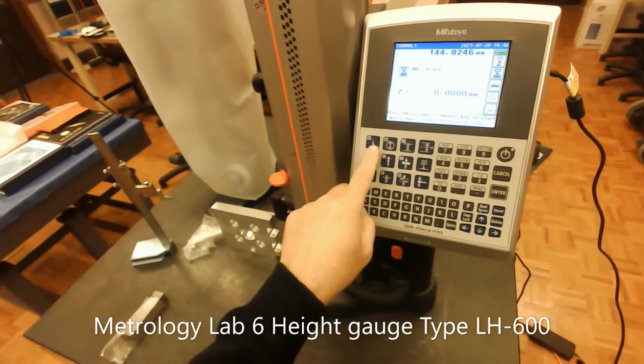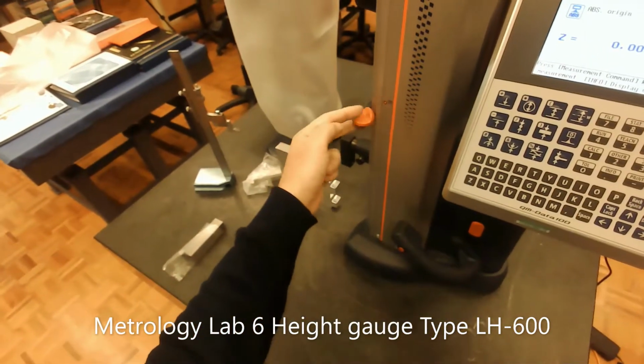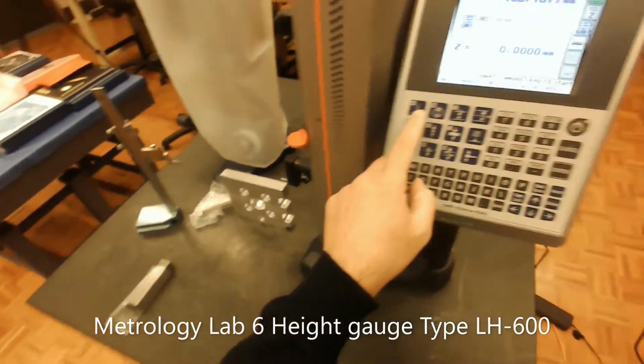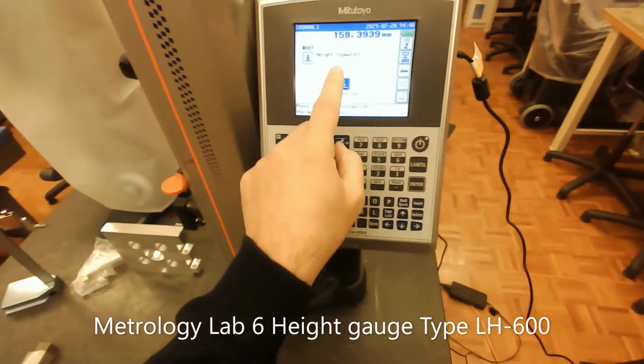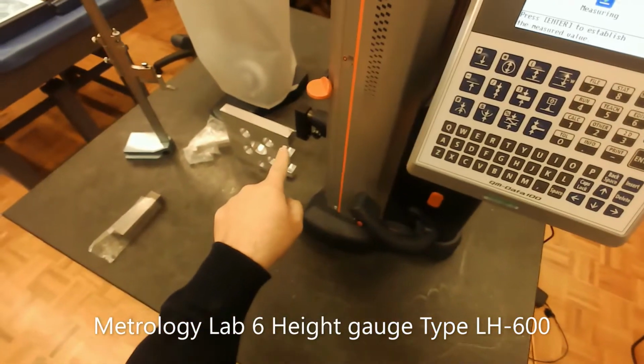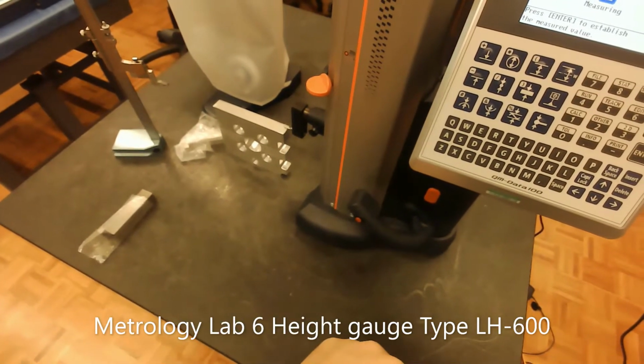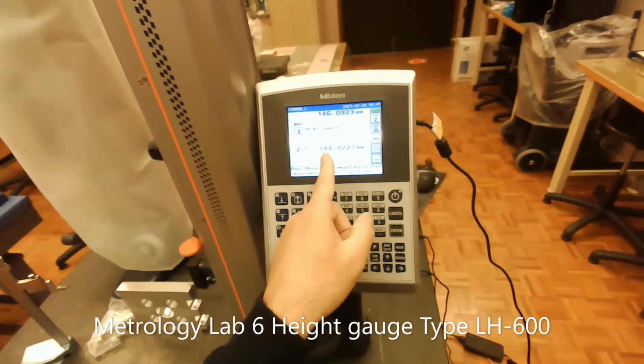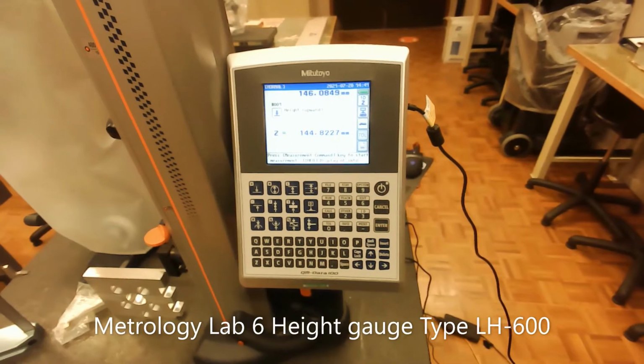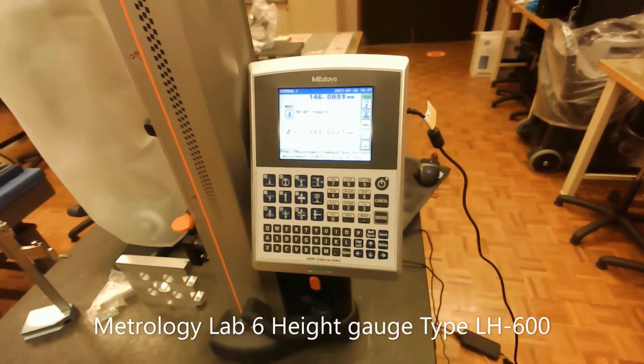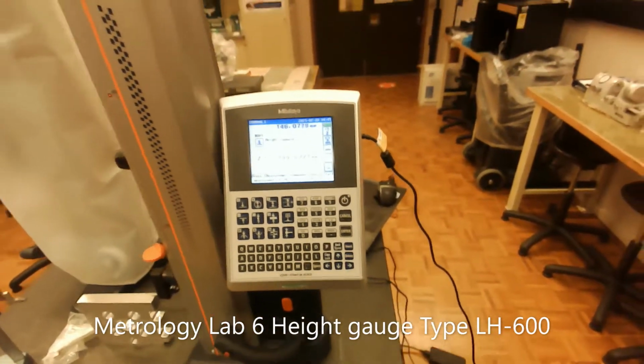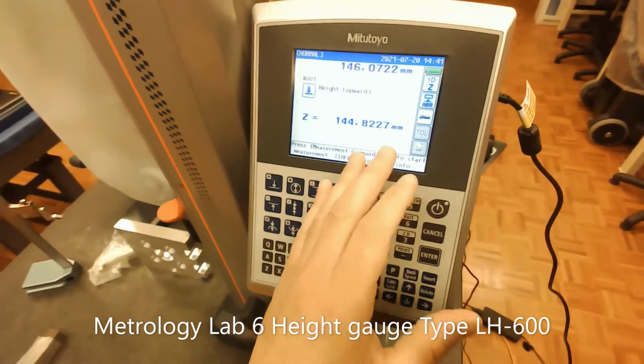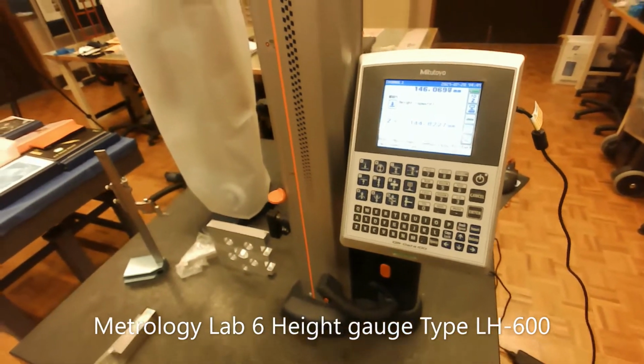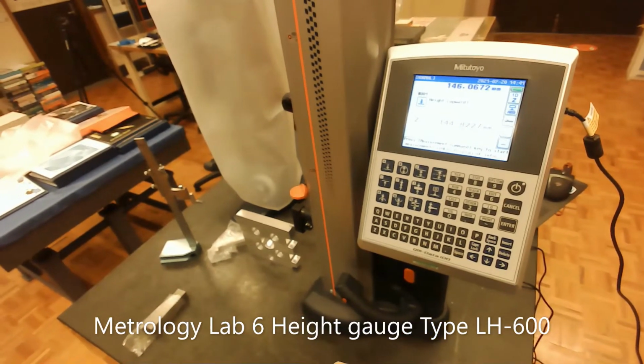this button. So if I take this one a little bit up, you will see what happens when I press this one. It's telling you that this device is going down, the probe is going down, to touch the surface. When you hear the beep, it's going to give you the reading here. So it's 144.8227. Now you can see that the reading is given in ten-thousandths of a millimeter. That's very good accuracy.